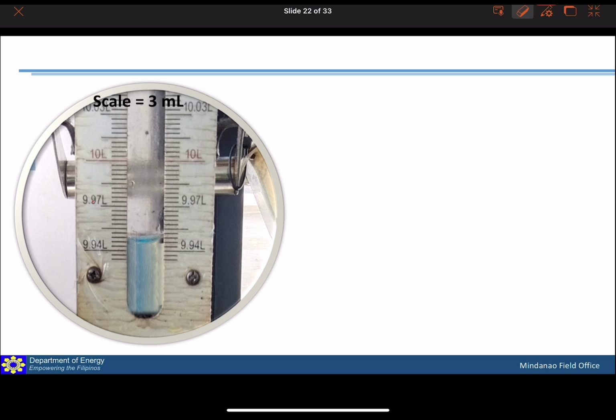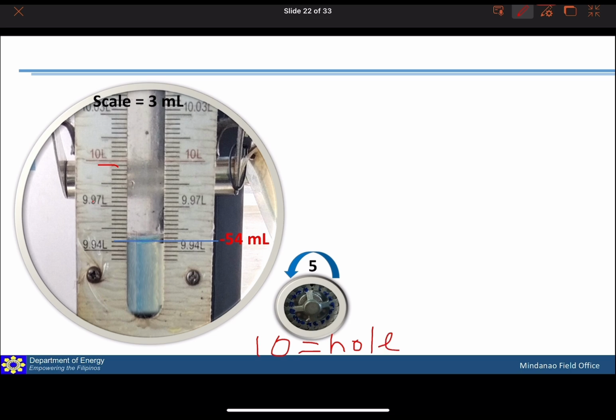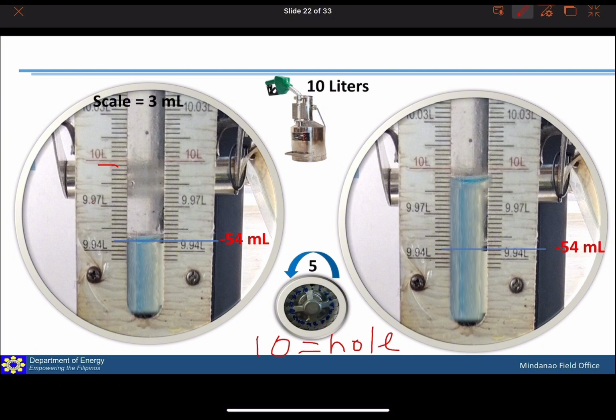Let's try calibrating bucket with different scale. So the scale of this particular calibrating bucket is 3 ml per hole. So the value of that per line is 3 ml. Therefore, the initial reading is negative 54 ml. So let's assume again na 10 yung value per hole. So we will adjust 5 times. After adjustment, mag-dispense tayo ulit ng 10 liters sa calibrating bucket. And our new reading is, our initial reading is minus 54 ml. Our new reading is minus 9 ml.